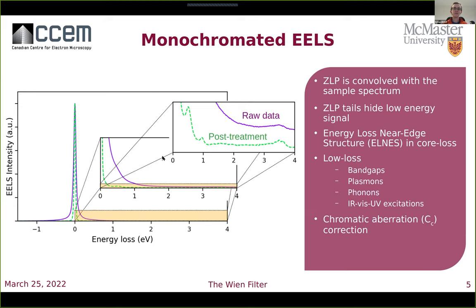In the low loss spectrum, the monochromator has a huge advantage because we're now able to study excitations down to the infrared, visible, and UV region of the spectrum, which can include excitations in the valence electron structure or atomic vibrational modes, really revealing a whole new world of excitations to study. The monochromator helps us study this region both by improving the energy resolution and by reducing the tails of the zero loss peak. Another use of the monochromator is as a chromatic aberration corrector — reducing the energy spread of your beam reduces chromatic aberration and can improve the spatial resolution of a high resolution image.